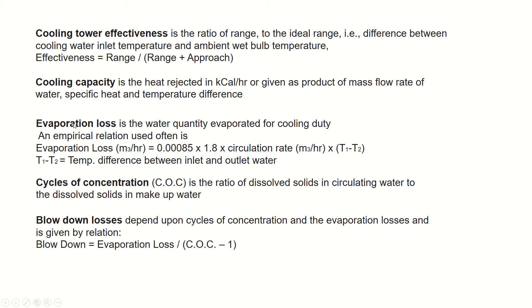The next term is evaporation loss — the quantity of water evaporated for the cooling duty, meaning the amount of water evaporated for a certain heat cooling requirement. The empirical relation used is: evaporation loss equals 0.00085 multiplied by 1.8, multiplied by circulation rate and the temperature difference.